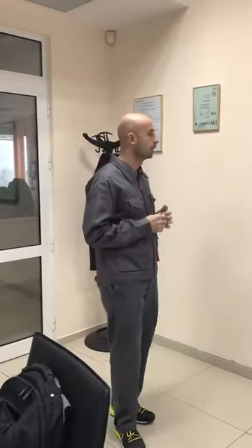We need to check if we have enough air changes ratio within the room, because when we talk about room temperature control, our main goal is the room. So we need to have enough air changes per hour, and the minimum one for us is 7 changes per hour. Also, it is very important to have a backup heating. Why? We need it for our startup mode, for the rapid heating when the temperature in the room is very low. So everything is possible, but we need to be honest and we need to be careful with that.